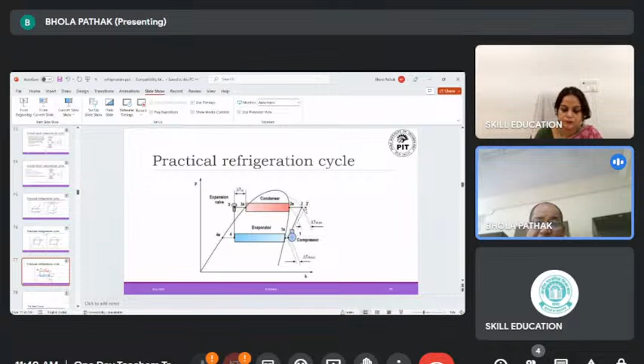So this is the pH diagram for this actual cycle. The same we have done. We have established on this pH diagram the different components. Here the compressor. Now 1 to 2 is the ideal compression. 1 to 2 dash is the actual compression. Now 2 to 2s is the desuperheating. Now here we have installed the condenser. Now 3s to 3 is the subcooling, and at point 3 we have installed some sort of expansion device. So, the expansion valve.